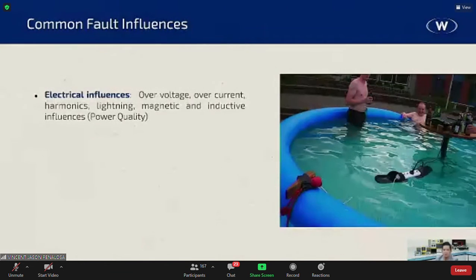First of all, you have the electrical influences. Whenever you have overvoltage, overcurrent, harmonics, lightning, magnetic, and inductive influences, if you have lousy power quality, chances are you also compromise the integrity of your insulation. Because what happens to a particular load, a cable, a bus bar, a circuit breaker, whenever you have overvoltage? They usually heat up. How about whenever you have overcurrent? Same thing. Whenever you have a high level of current harmonics, it also heats up a particular load, a particular protective device, and so on and so forth. And the rest of it is the same, right?